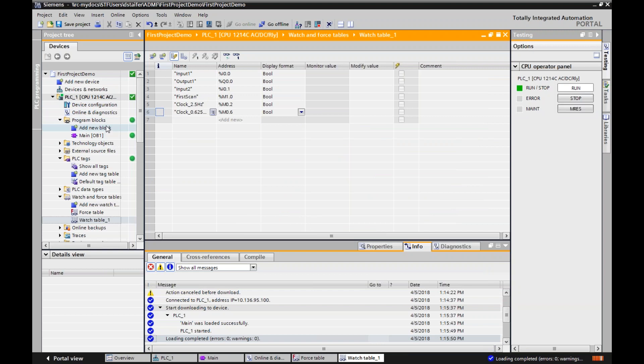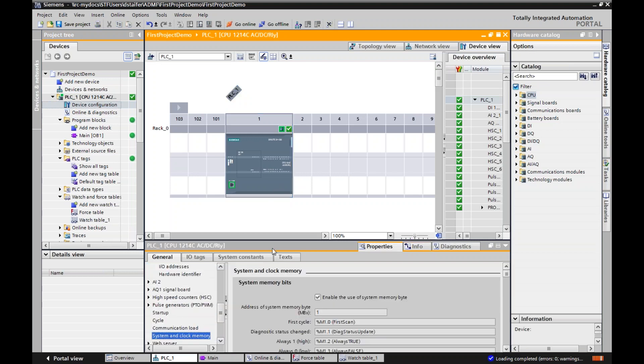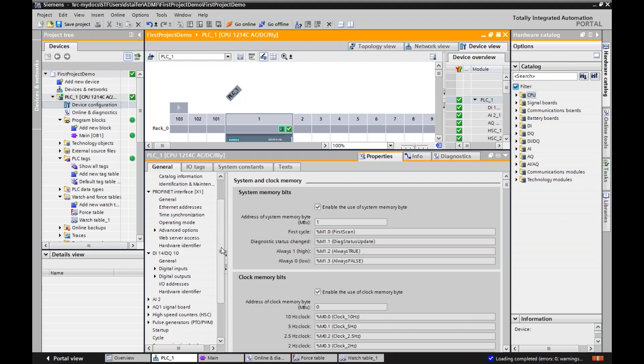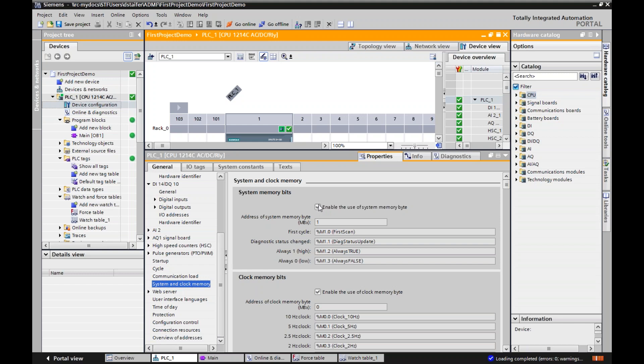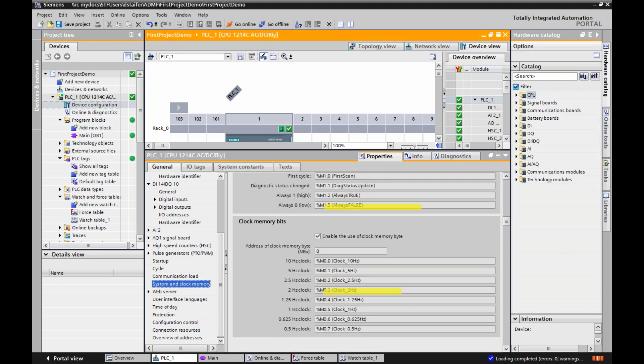Now in Siemens, I'm going to do a little bit of backtracking. If I go under device configuration and double-click on the PLC, down here in your general menu you can go down under system and clock memory bits. If you highlight both of these checks right here, the system will automatically populate some various system memory bits and clock memory bits that you can utilize in your program — things like first scan, or if there's a diagnostic status change, like maintenance mode, or from start to run, or different clock bits. So if you want a blinky light, you can use these clock bits, as I'll show you in a second.